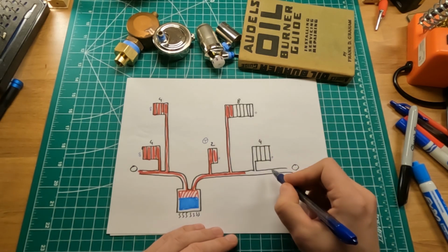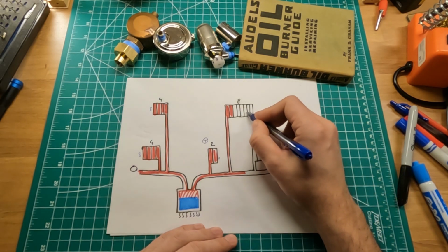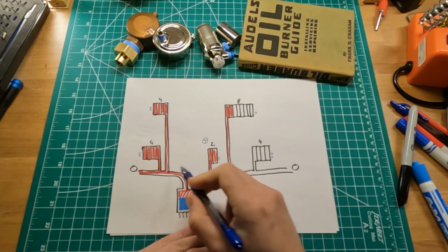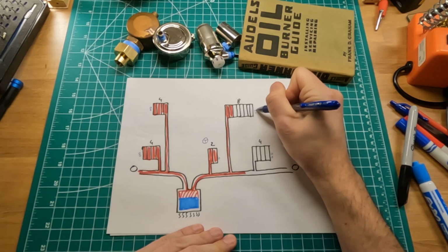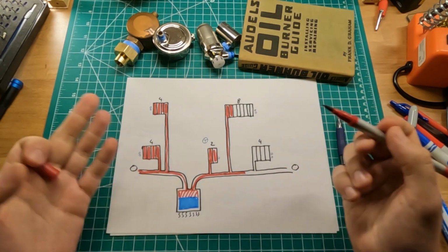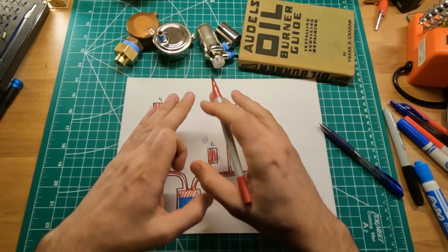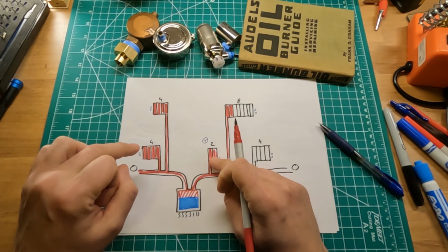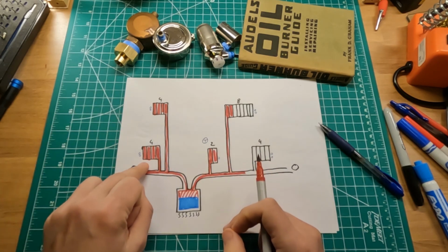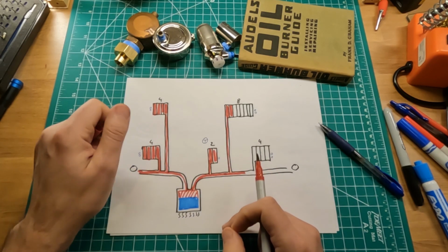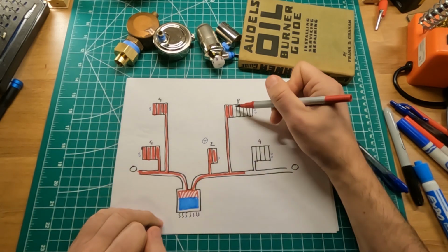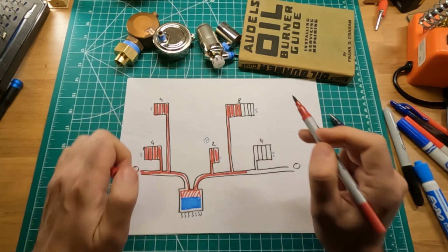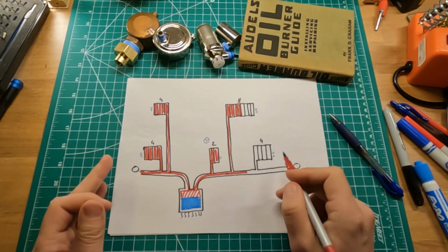If we increase the venting rate with this radiator, and this one as well, to the exact same rate as this radiator and this radiator, then by basic logic, in the same amount of time when the steam gets produced, this radiator heats up fully, this one heats up fully because of double venting, and this radiator heats up halfway across because it has the same venting rate as this one, and this one still stays cold even though you increased the venting.